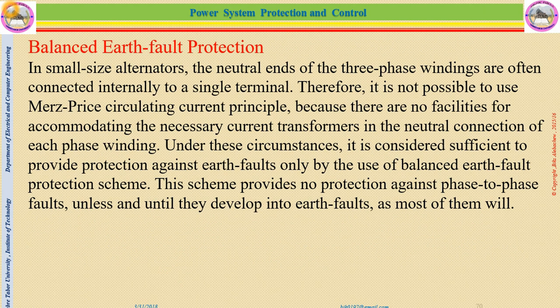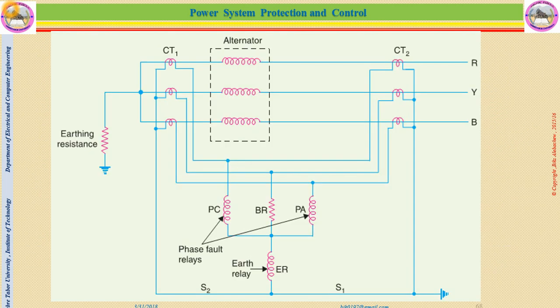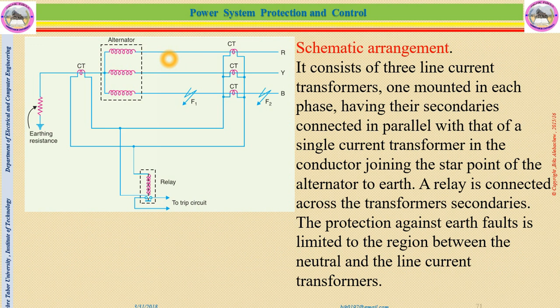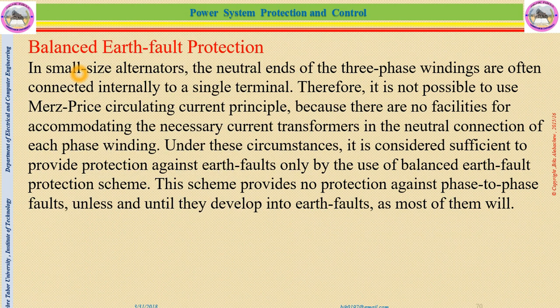Okay, balanced earth fault protection. In small size alternators or generators, the neutral ends of the three-phase windings are often connected internally to a single terminal. Remember from the previous classes, those terminals are connected in each phase. But in small generators, they may not be; instead, they are connected at a single terminal.